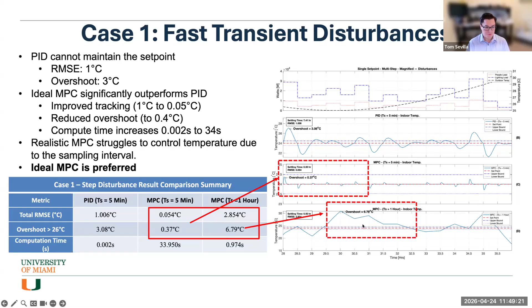And then when you look at the realistic MPC, you also have this struggle to maintain the set point. The reason here is not because MPC is performing poorly because of the control type, it's mostly because of the sampling time. Since our sampling time here is 1 hour, it's not able to capture these fast dynamics of 30 minutes that we see between our disturbances. Considering that we have such a long sampling time, by the time it samples again, it's not able to see what the current state of the system is, and then eventually overshoots. Hence, you have that very large, like 6.8 degrees C of overshoot. So in this particular case, the ideal MPC is a much better type of control, but obviously at the expense of computation time.